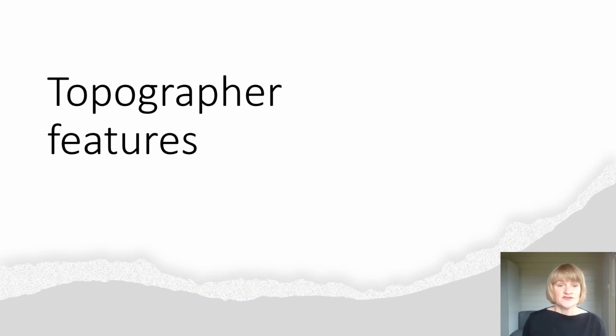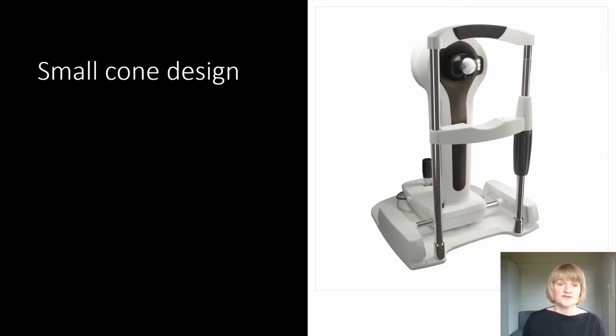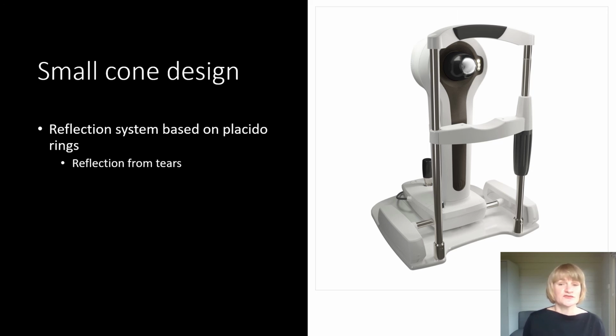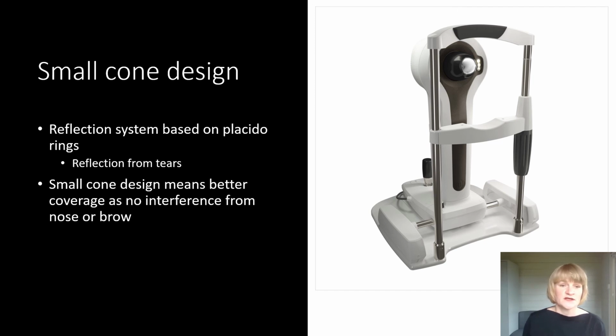So looking at the features of the topographer itself, it's a small cone design and it's a reflection system based on Placido rings. This means that you're reflecting from the tears, and it does mean that you'll need a good quality tear film to be able to get an accurate representation of corneal shape. The small cone design means that you get better coverage than a large cone design because you have no interference from the nose or the brow.